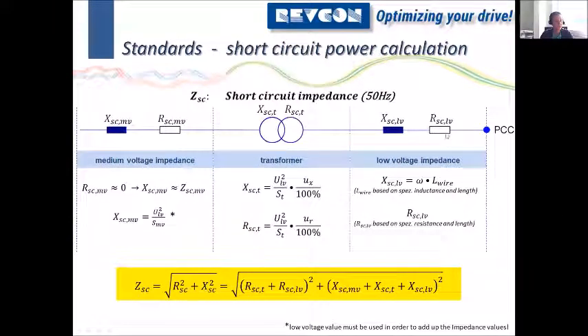Okay, so this is the full calculation that you would need. You would need the medium voltage impedance, you would need a transformer impedance, the voltage impedance, and then you just hit it into the calculation, and very easy, you will get the result. But even if you have this equation right with you, to get these values, it's more or less impossible.